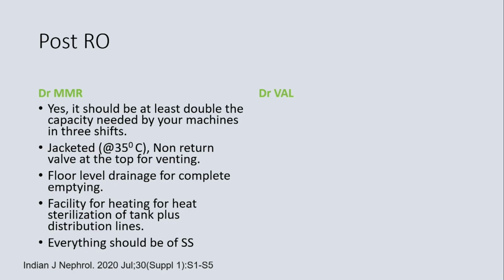When you are doing heat sterilization, I made a bad mistake. This time, in the last system, I forgot to tell them to do stainless steel welding, because we added a heating element to the tank. What happened was, the first time we started doing heat sterilization, all the welded joints gave way and the whole dialysis unit was in a water pool. And then, because many of those pipes were concealed, nobody would allow me to change that altogether. So we still got back to chemical sterilization of the loop.